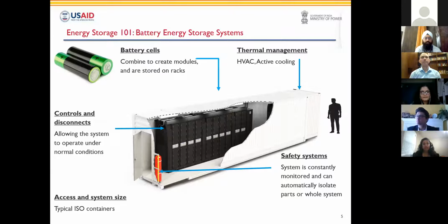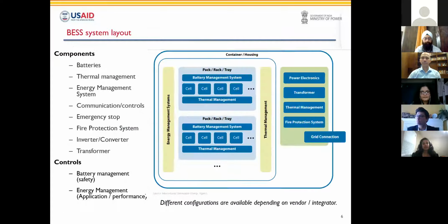Moving on to the next slide, looking at the bigger picture. The schematic on the right is a representation of a very high-level storage system at a project level. The inner box represents the container we were just looking at. Typically, there are several containers depending on the size of the storage system. These are then connected to power electronics equipment like inverters, much like PV system inverters, transformers, switchgear, and other auxiliary electrical equipment to connect to the substation itself.